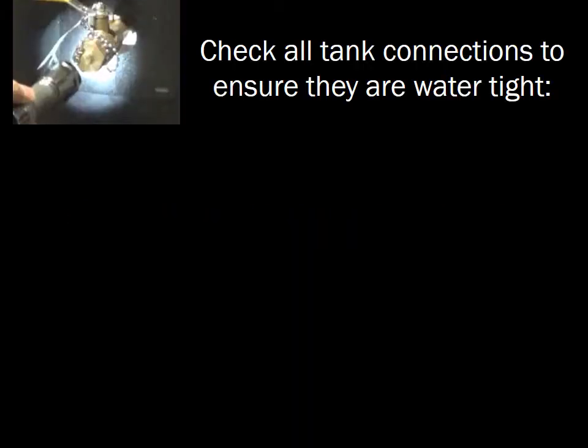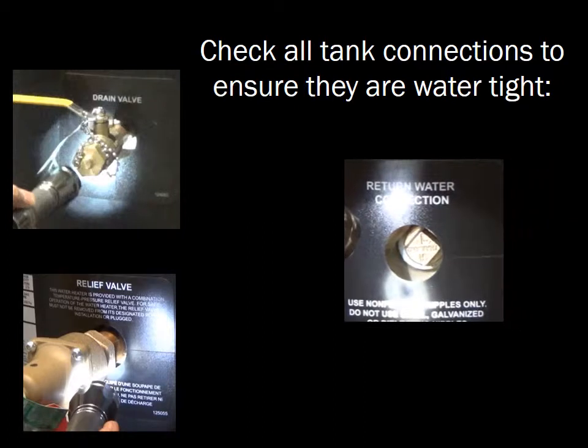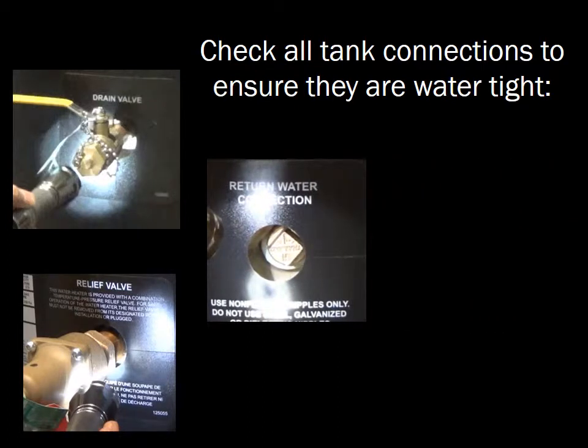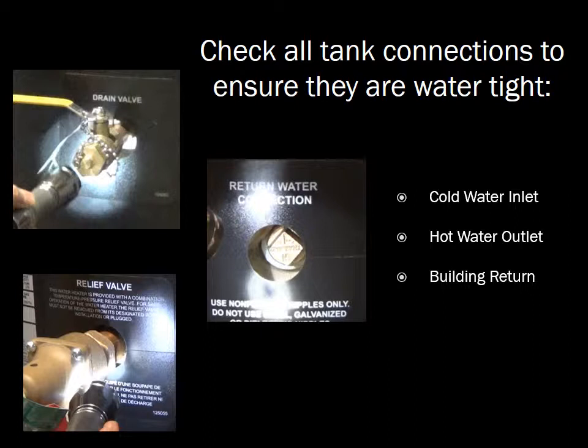When the tank is filled, check all tank plumbing connections to ensure they are watertight and tighten as necessary. Thread leaks will damage the tank insulation. These plumbing connections are located at the cold water inlet, the hot water outlet, the building return, the drain valve, and the relief valve.